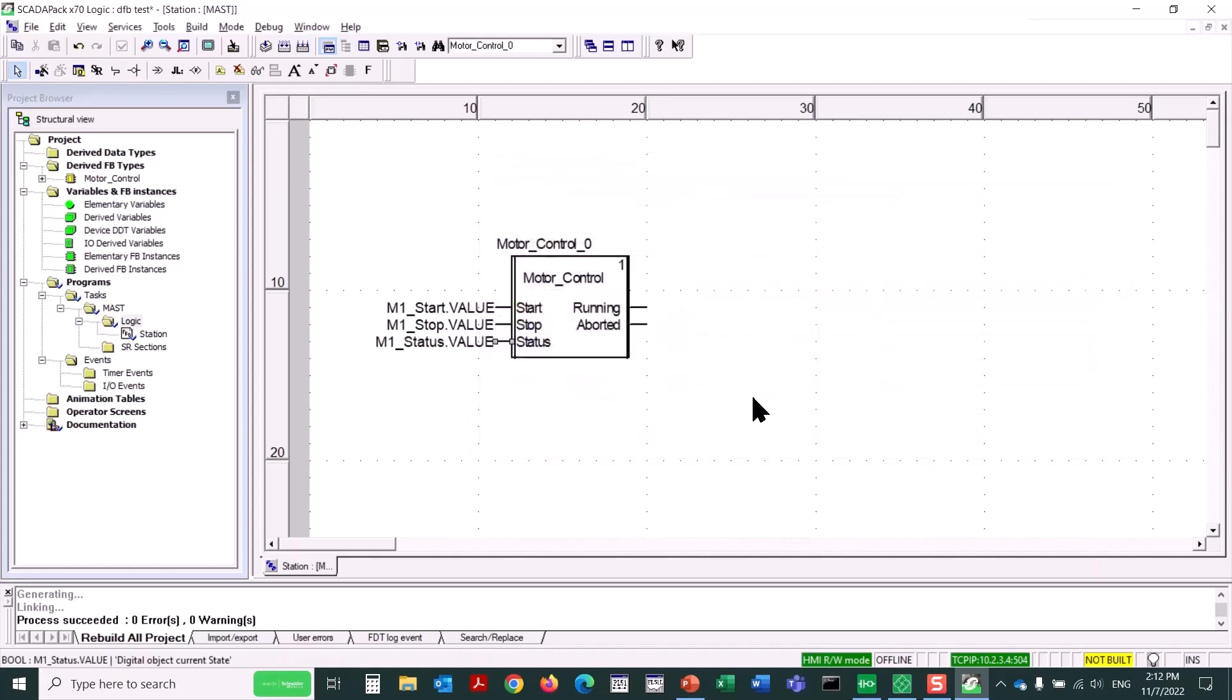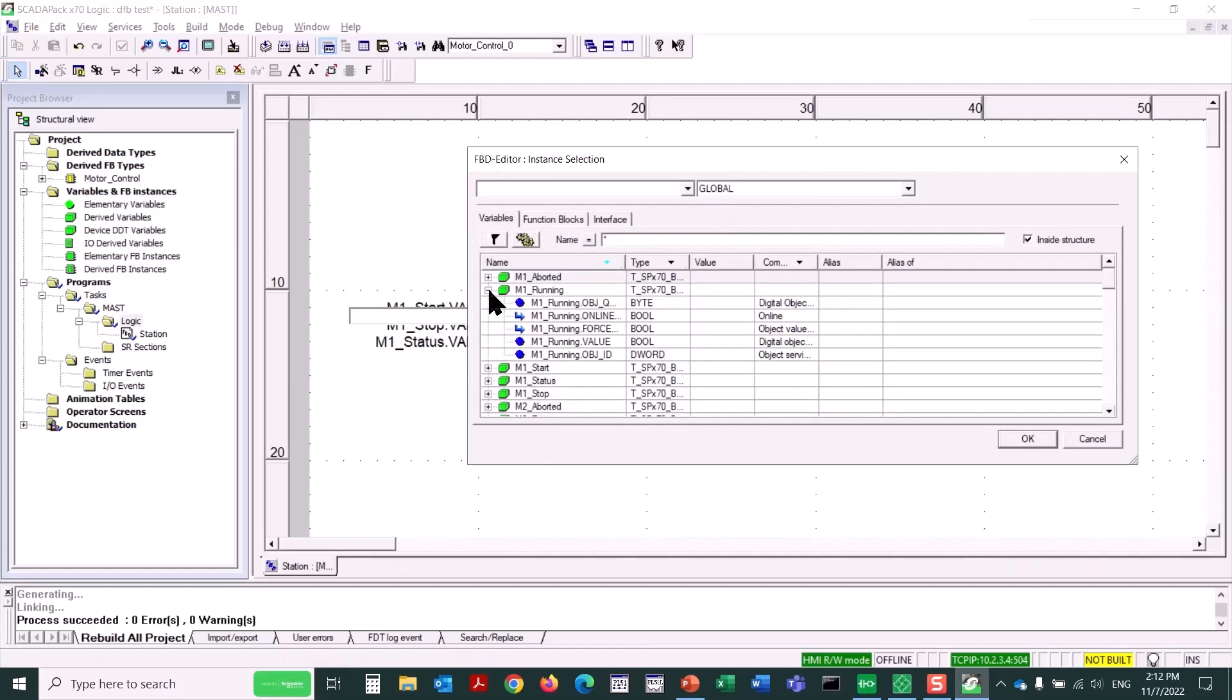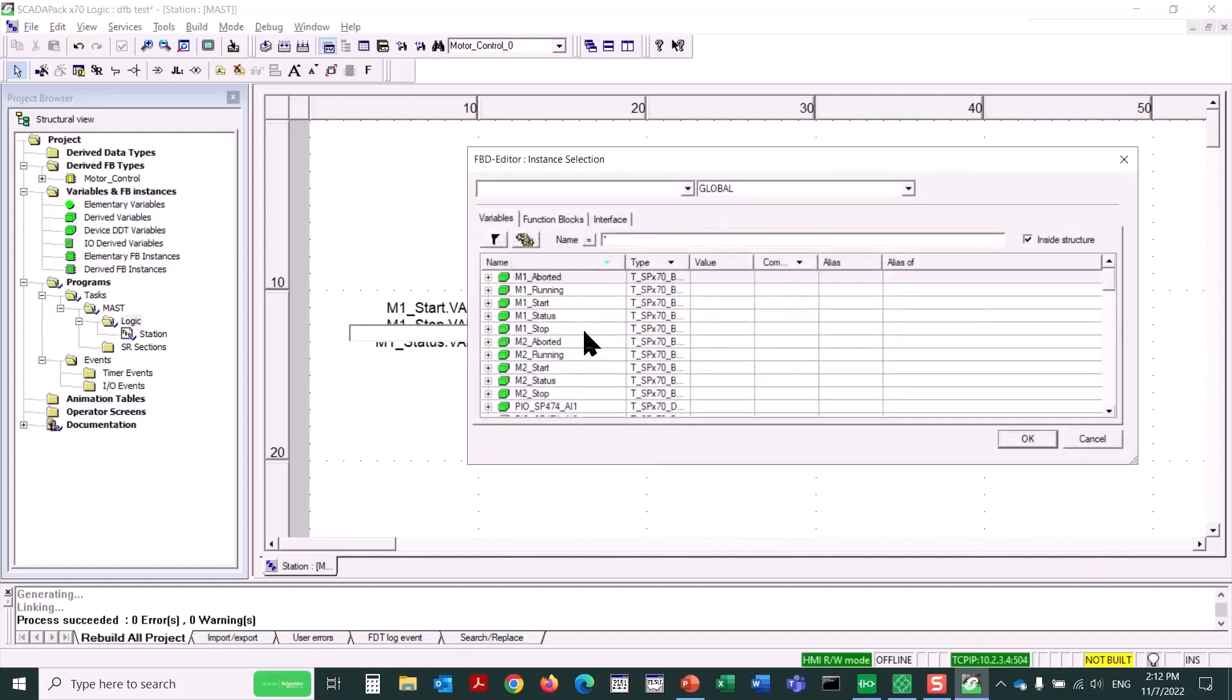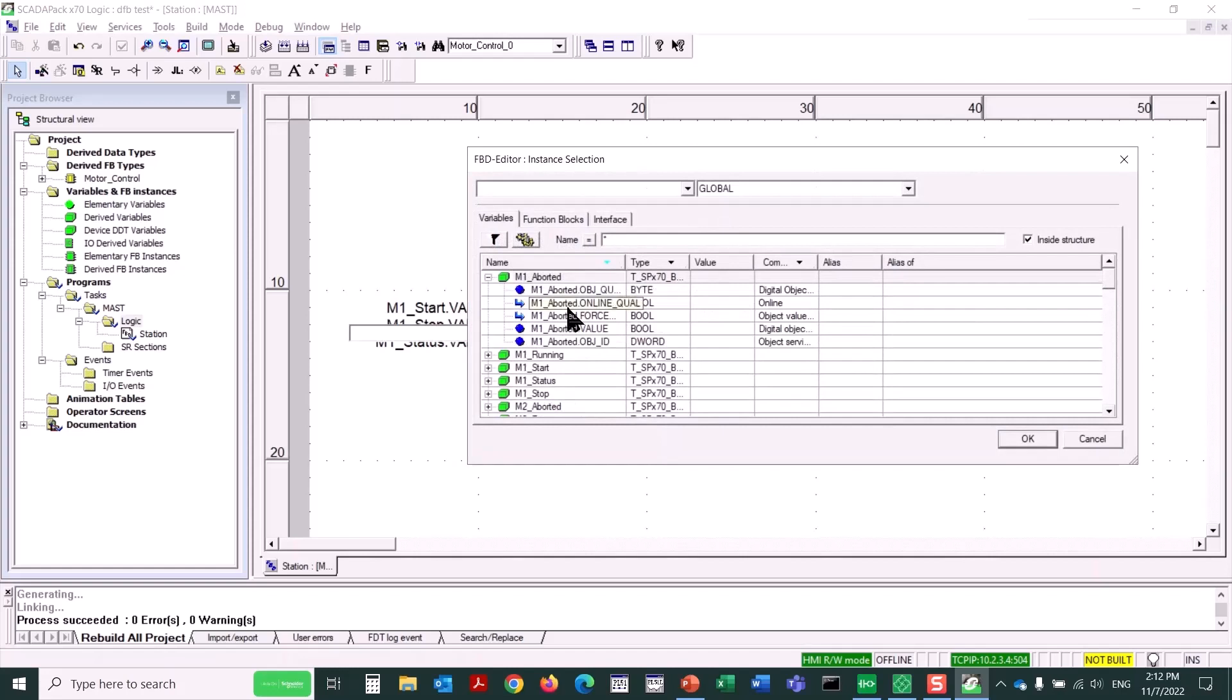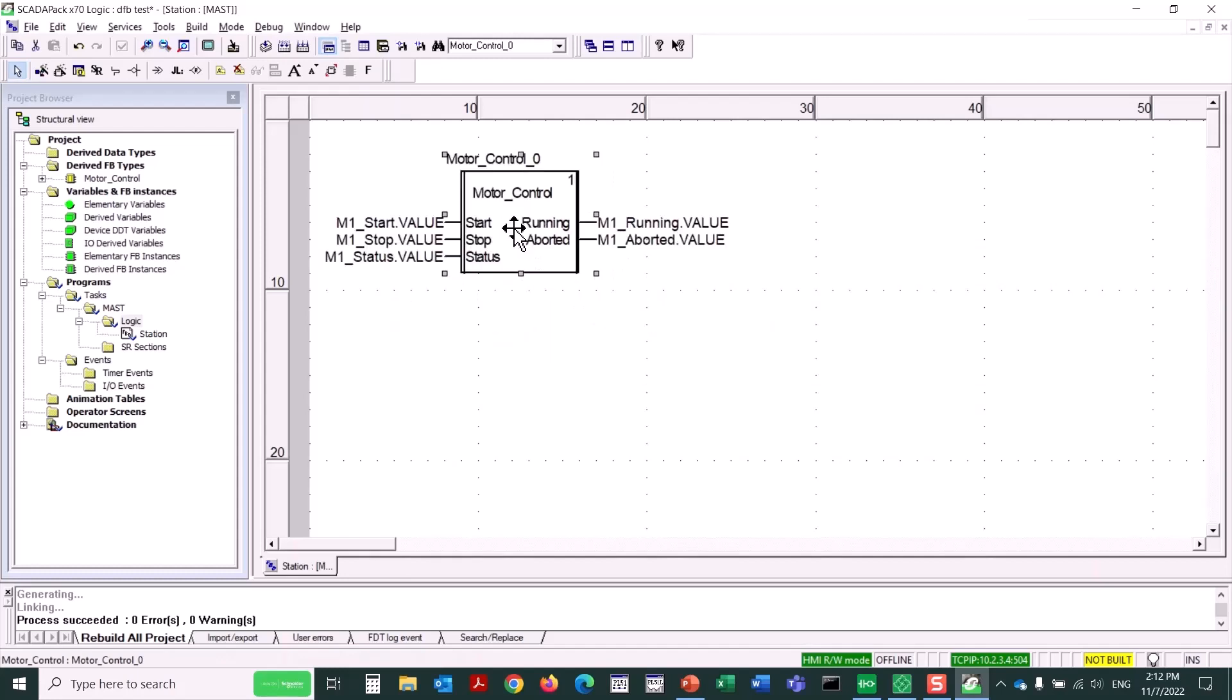And we just keep going. For the running output, that would control the motor, we'll select M1 running dot value. And for the aborted output, this is if the timer reaches its full value of 5 seconds, we'll pick M1 aborted dot value. So there we have this function block fully populated. I can click on it, move it around a little if I like.